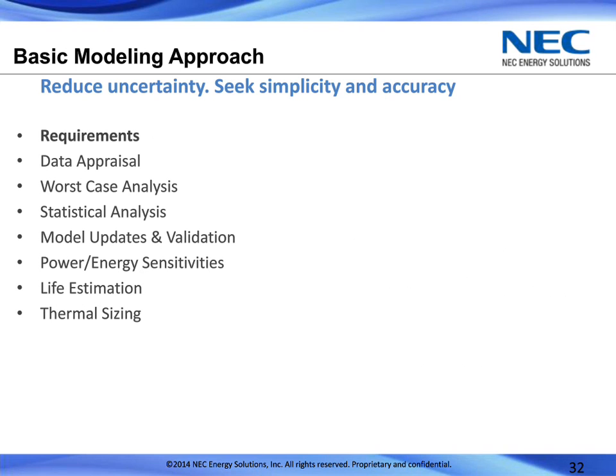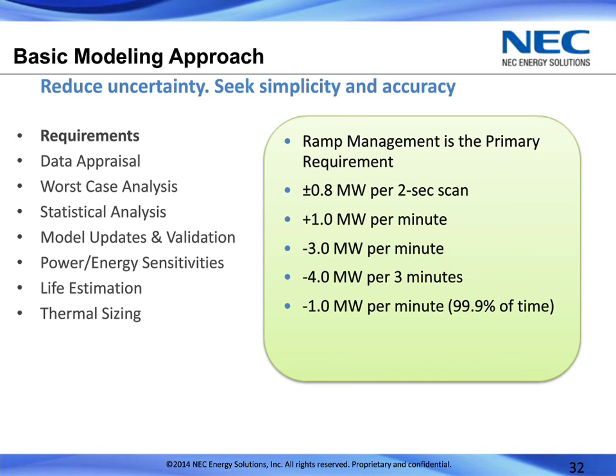So looking at the requirements part of this process, again, this is a ramp management requirement for this facility. The 1 megawatt per minute ramp rate you see in the list is represented as a plus 1 megawatt per minute and a minus 1 megawatt per minute. There are also other ramp rate requirements. There's what they would call an instantaneous change, where between their 2-second samples of data, they want less than 0.8 megawatts, and then over longer time frames, there is an allowance to violate the 1 megawatt per minute ramp, but not certain higher limits. And these are basically set up based on what their traditional generation fleet can compensate for.